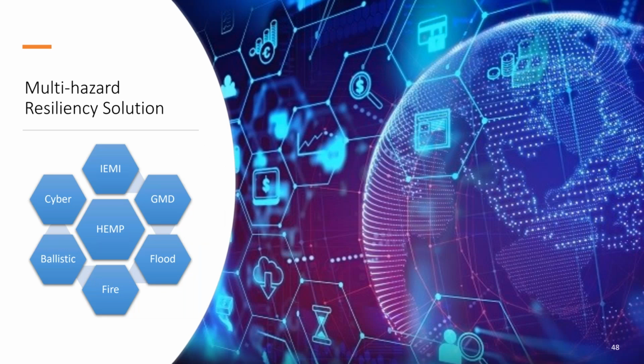And then lastly, just here in the center, we started working on a HEMP solution, which then turned into IEMI and GMD. But because of the compactness of the module and the consistent hardware, we're actually able to redeploy that for other high impact, low frequency events, such as floods, fires, ballistic events. In doing so, we also went to the digital platform, which created a cyber concern, but we've also solved the cyber issues as well. So we think it's a very holistic approach that allows us to mitigate multiple hazards with one solution. And with that, I'll give it back to Frank.